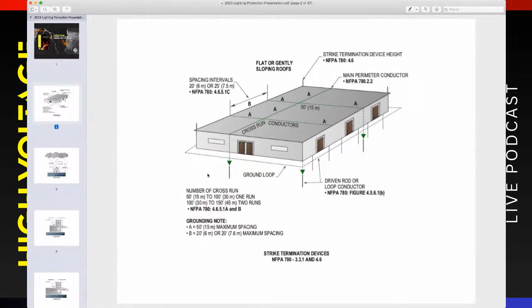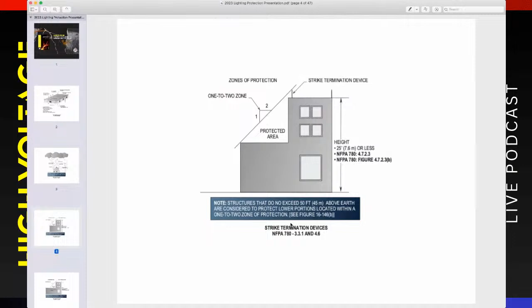It's pretty interesting because we actually talk about the rolling sphere and the radius developed above the building if you get lightning strikes outside with your strike termination devices. As you go in, we look at heights of buildings, and you can see what area is protected or not protected, whether it's a 1-to-1 zone or 1-to-2 zone. We literally break down every bit of that for you.